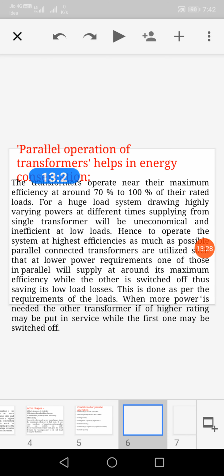Parallel operation of transformers helps in energy conservation. How does it help us with energy conservation? Transformers operate near their maximum efficiency at around 70% to 100% of their rated load. For a load system drawing highly varying power at different times, supplying from a single transformer will be uneconomical and inefficient at low load.